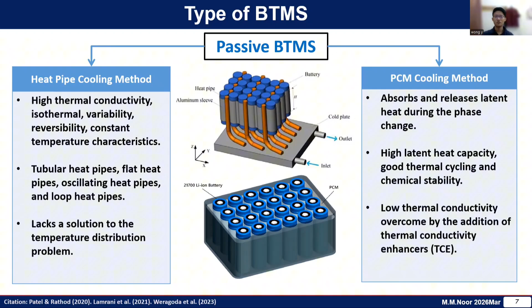In PCM cooling methods, usually organic PCM is used, such as paraffin wax. It has high latent heat capacity, good thermal cycling, and chemical stability. But PCM has low thermal conductivity, so engineers usually add a thermal conductivity enhancer or composite, such as reduced graphene oxide, expanded graphite, and metal foam, to increase thermal conductivity.